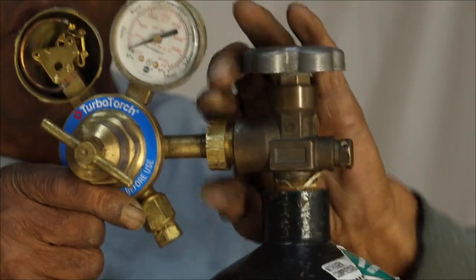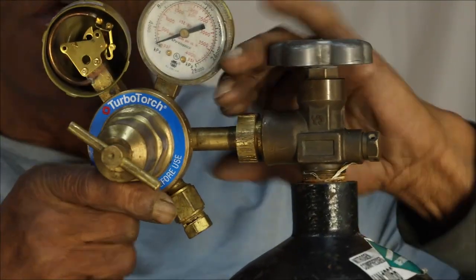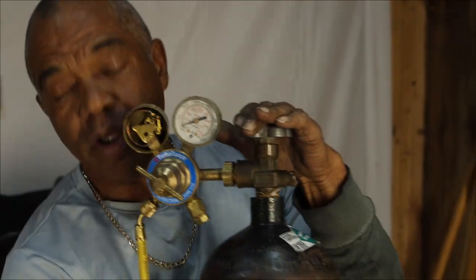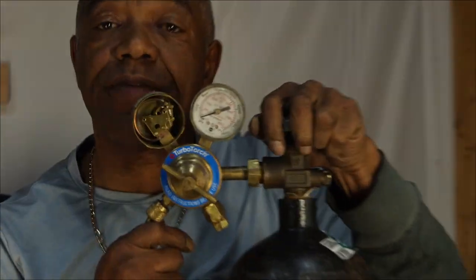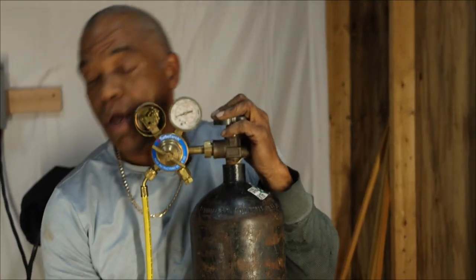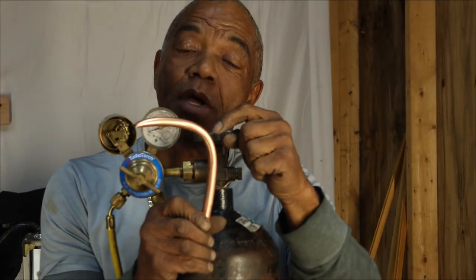In most cases, that is easily taken care of by hooking my regulator up to my nitrogen tank, hooking my gauges to my system, and filling that system with 300 PSI. I can fill it with more, but normally at 300 PSI, wherever that leak is, I'm going to hear it. 300 PSI inside a small copper tube, if there's a pinhole, you're going to hear that air.